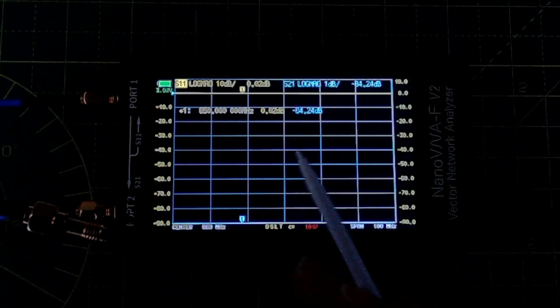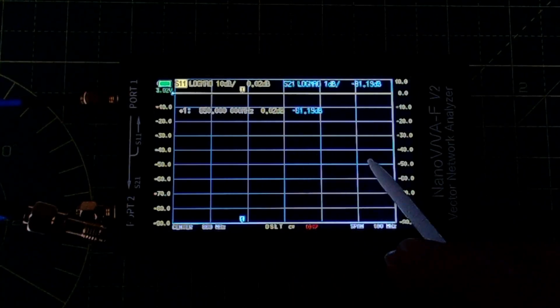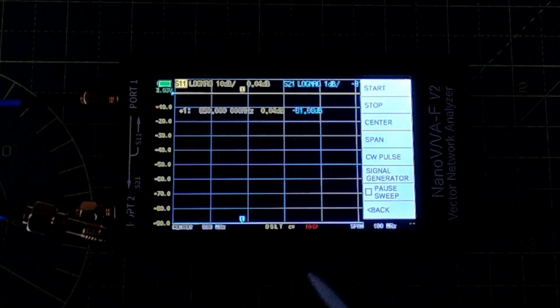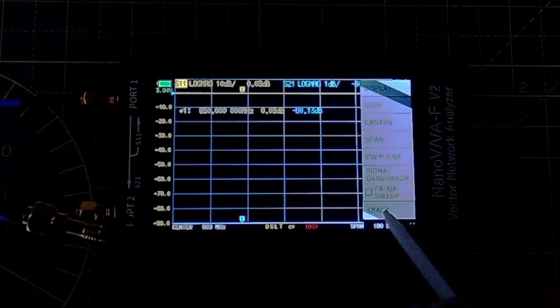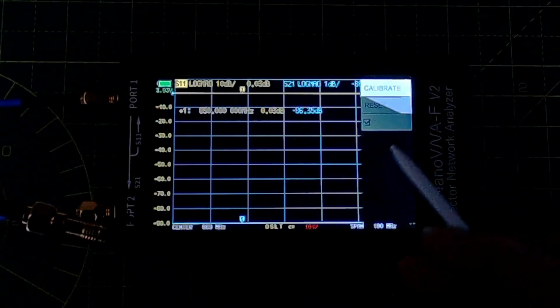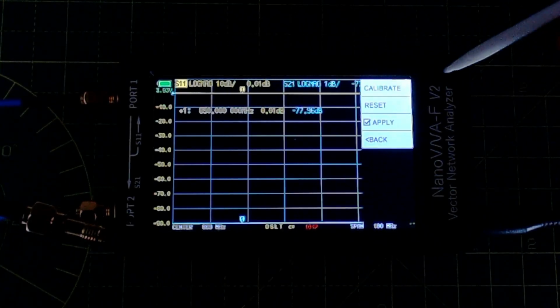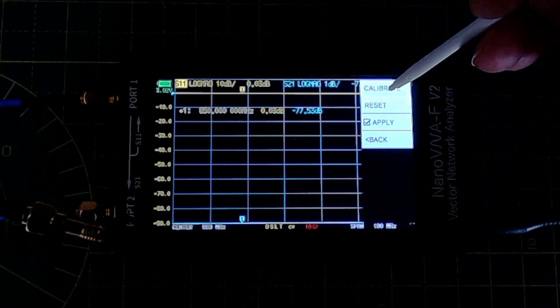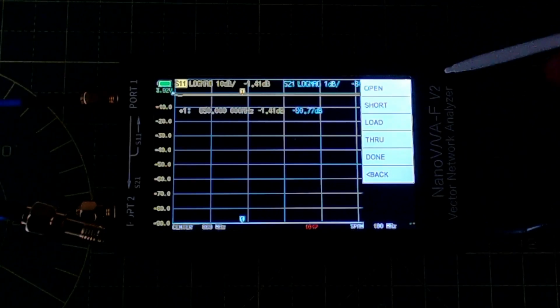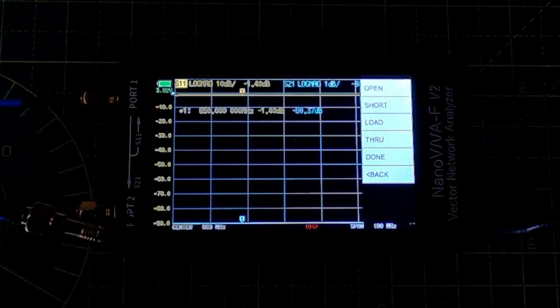So now we can do the calibration. So you just follow the instructions on the screen, which are a little bit cryptic, but how do we do calibration? Go back, cal, and then you have to hit the button that says calibrate, because I want to calibrate this first. And the first thing it wants in the list is an open circuit, and you can actually get an open circuit SMA connector.